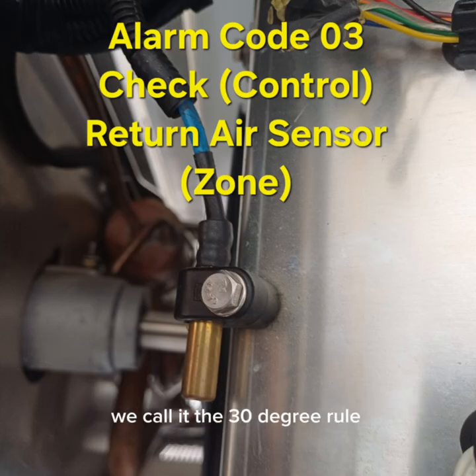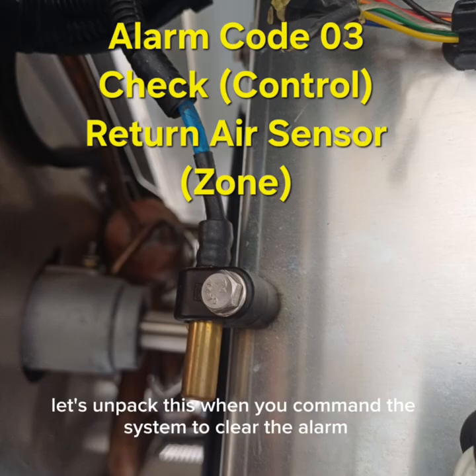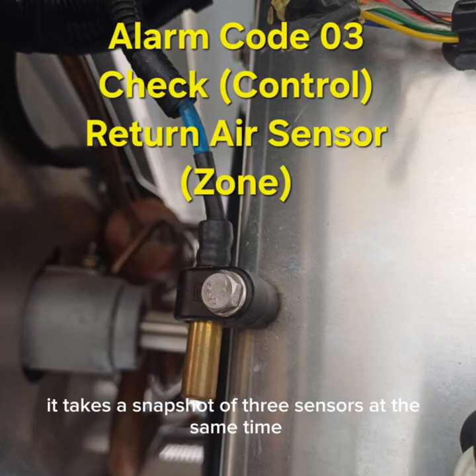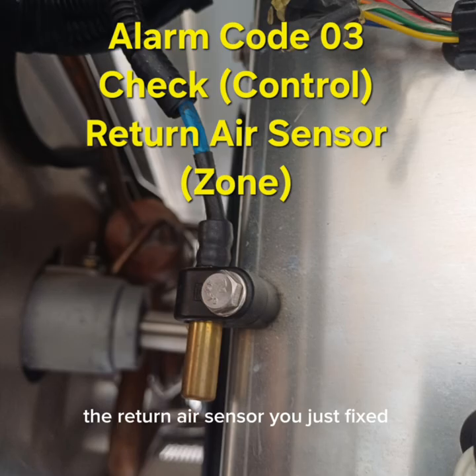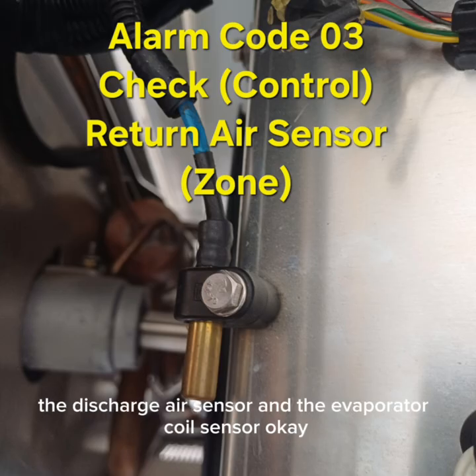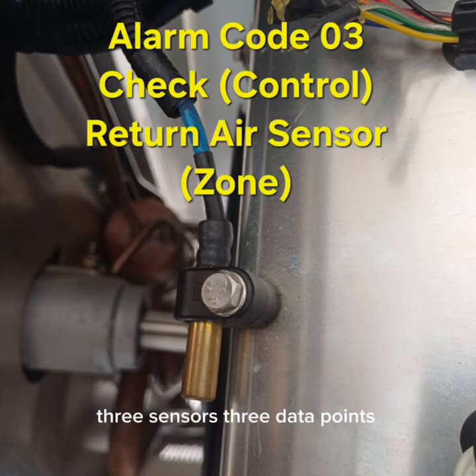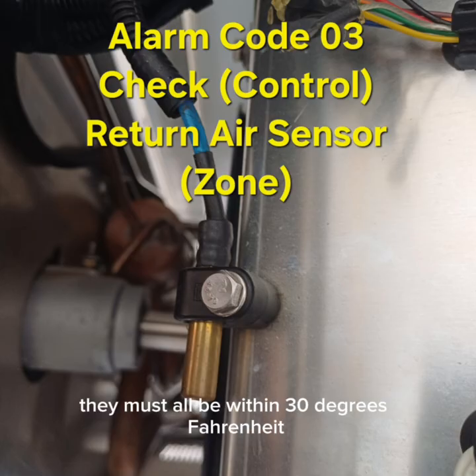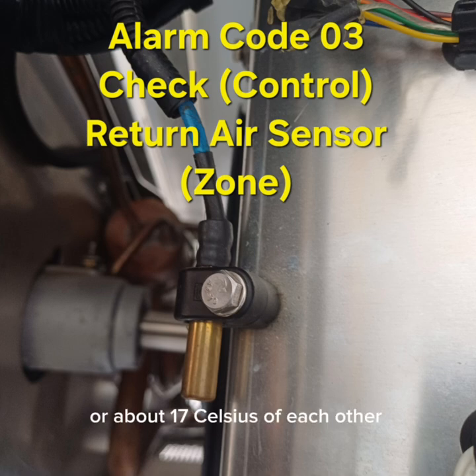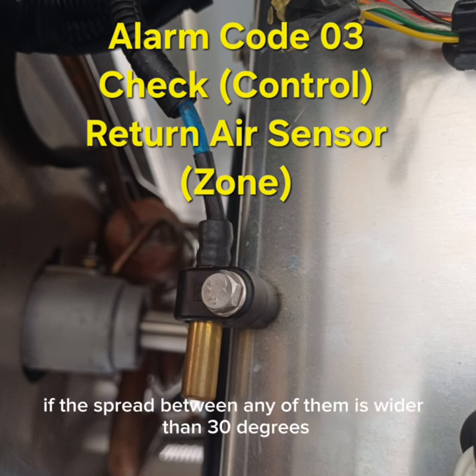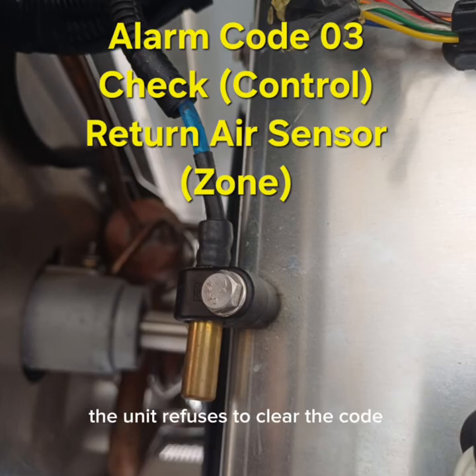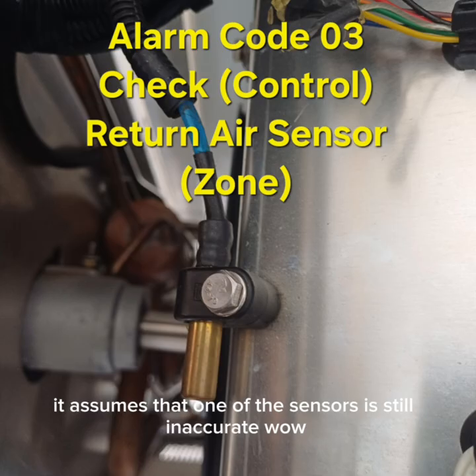We call it the 30-degree rule. The 30-degree rule. Okay, let's unpack this. When you command the system to clear the alarm, it takes a snapshot of 3 sensors at the same time. The return air sensor you just fixed, the discharge air sensor, and the evaporator coil sensor. Okay. 3 sensors, 3 data points. And it compares their readings. They must all be within 30 degrees Fahrenheit, or about 17 Celsius of each other. All 3. All 3. If the spread between any of them is wider than 30 degrees, the unit refuses to clear the code. It assumes that one of the sensors is still inaccurate.